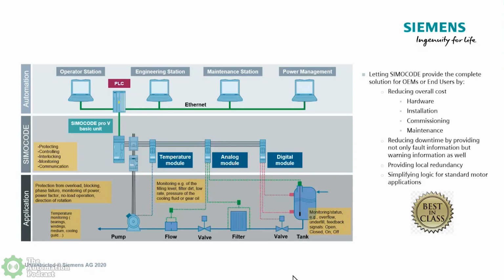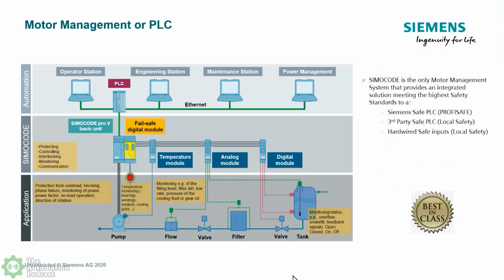And now it'll be able to run standalone if needed, or it can continue to communicate with the PLC and give all the information that's going on in that application. And then one last extension of that is the safety factor. So we can do safety depending on your application, but we can do any of the safety that is required with your plant. If you're using the safety specifications for SIL, safety integrity level, SIL level 1, 2, or 3, or if you're using the specification for performance level A, B, C, and D.